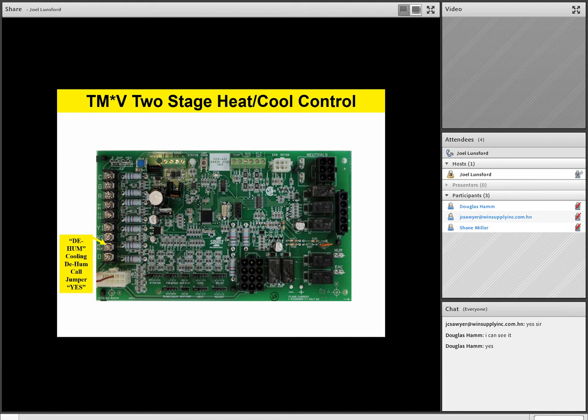Now this is really, really important. If your contractors call in and say, hey, I don't have anything hooked up to that dehume terminal, what do I do with that humidistat jumper? You want to make sure it's in the no position if you're not going to utilize that circuitry. So make sure the humidistat is in the no position if you do not want to use that dehume function. Any questions or comments on that?